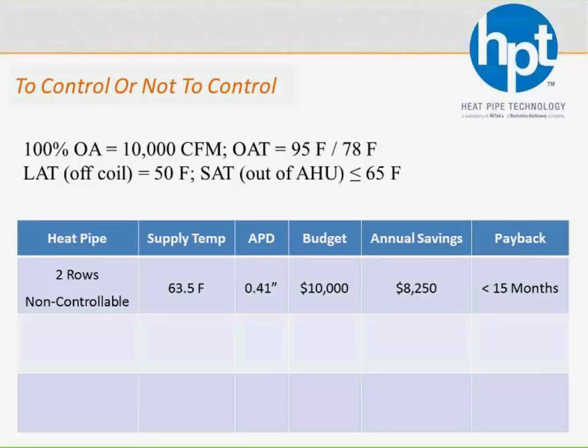Depending on where you're located, what utility rates are, and what kind of application and operating hours you're looking at, it's very common to see a 1 to 2 year payback with a wraparound heat pipe. And again, that's because you're not just saving on the pre-cooling side, and you're not just saving on the reheat side, you're saving on both. But the downside here, yes, you don't have to control it. You can let it run, do its own thing all the time, and it's never going to be too hot. But at the very least, even on the hottest day, that's 1.5 degrees that you're missing out on of free reheat. If you can get up to 65, well, every other day it's even worse. But even on that worst day, that's a full 1.5 degrees that you're having to pay for reheat.